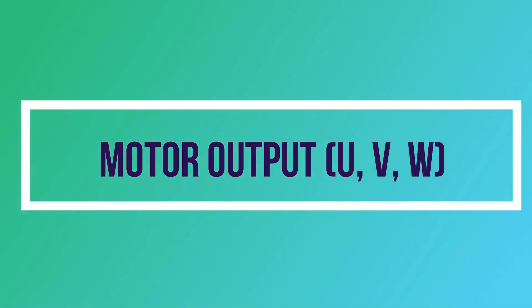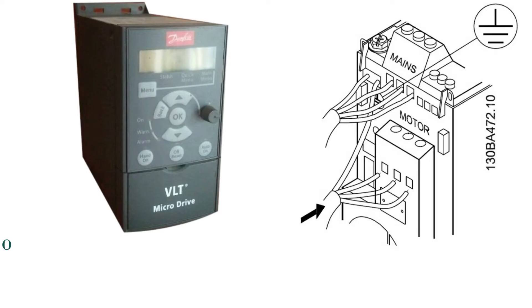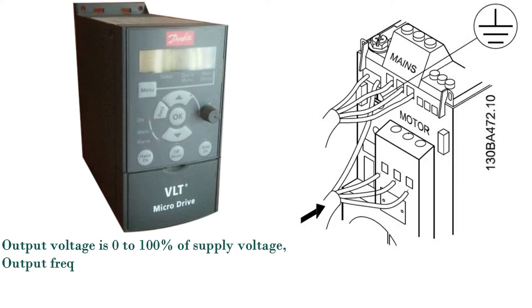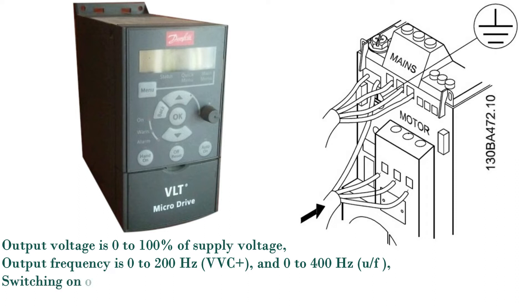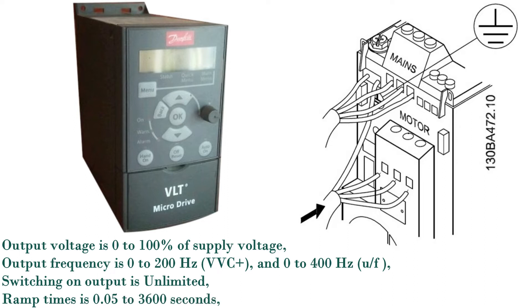Main menu button is used for access to all parameters. Motor output terminals U, V, W: output voltage is 0 to 100% of supply voltage. Output frequency is 0 to 200 Hz (VVC plus) and 0 to 400 Hz (U/F). Switching on output is unlimited. Ramp times are 0.05 to 3,600 seconds.